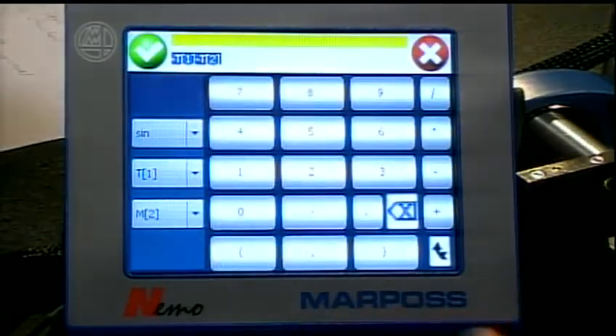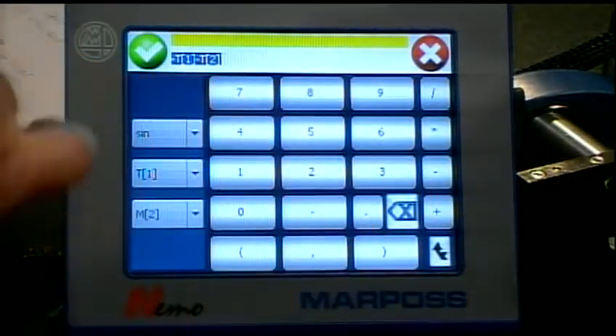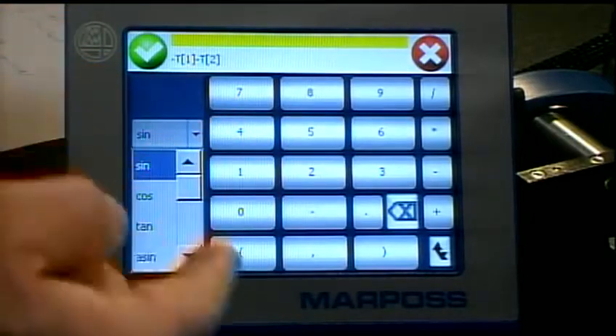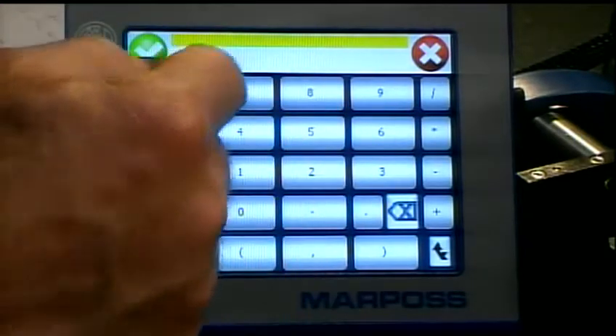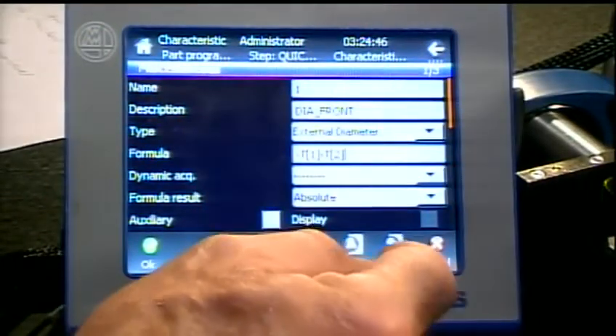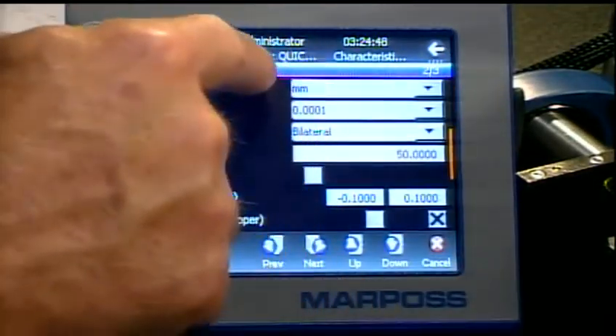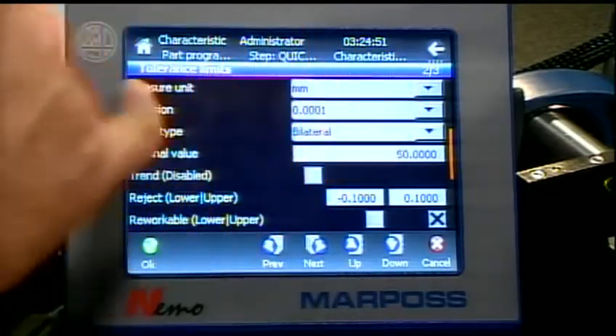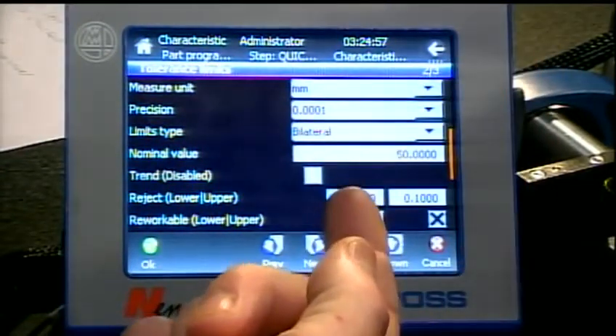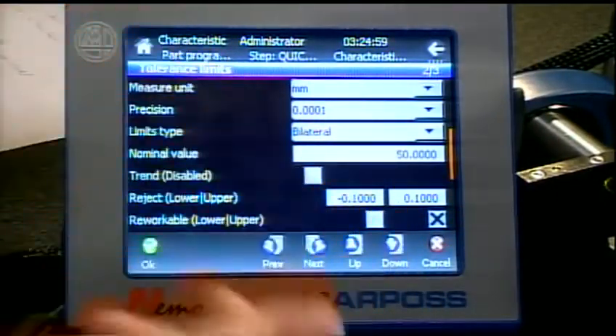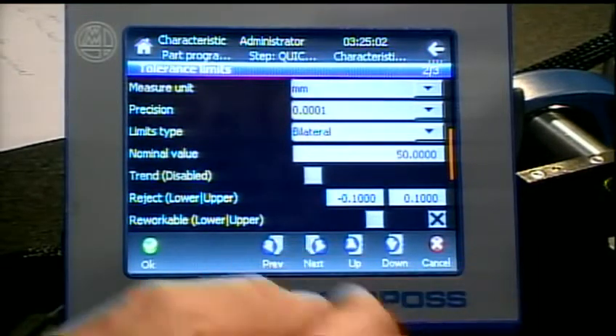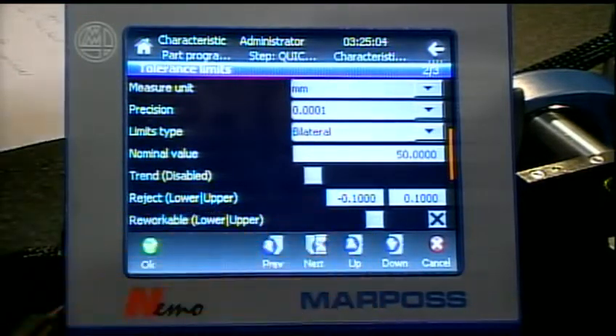Then there's the formula. What do we want to do with the data that we collect from the set of probes? So we have a bunch of functions that we can select from, sine, cosine, tangent, a bunch of trig functions, some other functions as well. But what we're going to do here is we're simply going to take the first probe, subtract it from the second probe to give us our diameter. We can move down. In our menu, we can set the measurement units, the precision, what type of limits, bilateral in this case, what our nominal value is, what our upper and lower limit are, 0.1 millimeters in this case. And then we can move on to our next characteristic.